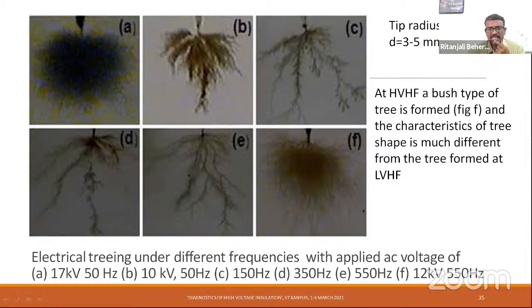The next set, C, D, E, are all stressed at 10 kV at different frequencies in increasing order: C at 150, D at 350, and E at 550. As the frequency is higher, they become more branchy, more fibrillar in type. The difference between E and F is that both are at the same frequency, but E is at 10 kV and F is at 12 kV - meaning at slightly higher voltage at the same high frequency, it becomes mostly a bush-branch type of tree. That is the effect of high frequency combined with high voltage.